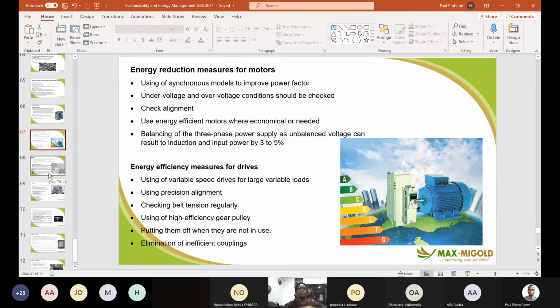And there are so many other energy reduction measures for motors. There are so many places where you have motors: your escalators, your elevators, your chillers. So many opportunities to look at how motors drain your energy. Use synchronous models to improve power factor. Under voltage and over voltage conditions should be checked. Check alignment. Use energy efficient motors where economical or needed. Balancing of the three phase. Phase imbalance is also a very big issue. Unbalanced voltage can result in an increase in input power by 3 to 5%, sometimes even more.